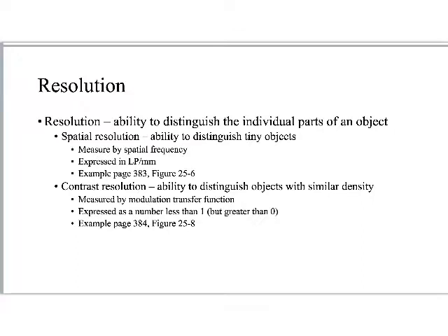As we're going down the lines and we're looking at where exactly do the lines become so blurry and indistinct that we can no longer tell where a black line starts and a white line begins. If I look at the large focal spot size, I don't scan down very far before the image starts to get blurry to my eyes. Versus over here on the small focal spot size, I can scan down further before the image gets truly blurry.